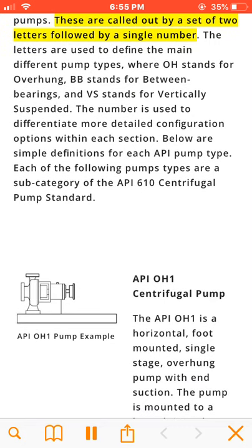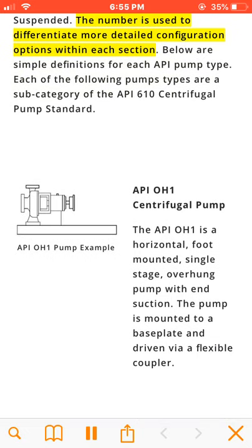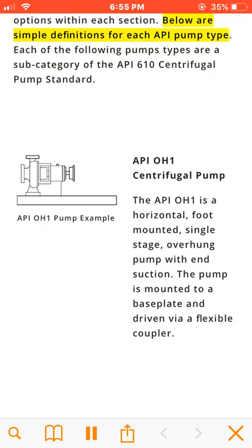These configuration codes are called out by a set of two letters followed by a single number. The letters are used to define the main different pump types, where OH stands for overhung, BB stands for between bearings, and VS stands for vertically suspended. The number is used to differentiate more detailed configuration options within each section.